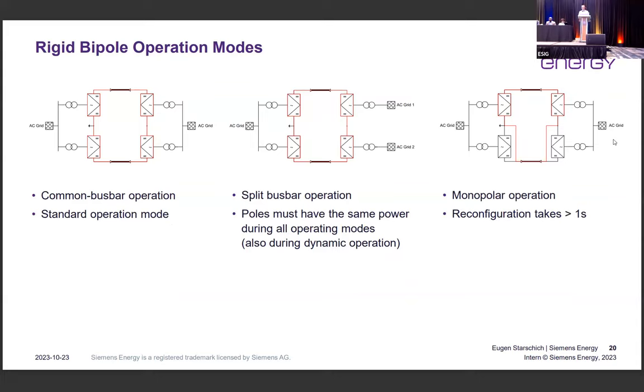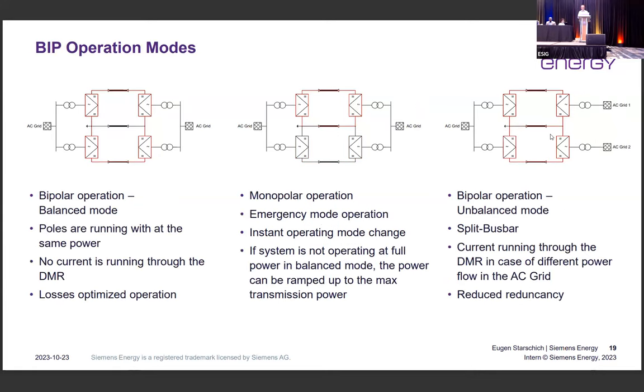In the rigid bipolar operation modes, it's very similar. You can also have a common busbar operation and split operation. One of the other features in the rigid bipolar, and this has been mentioned before, is that in case of a converter fault, you can reconfigure and bypass the faulty converter, as I've shown here, and then you can still transmit at least 50% of the power. So you've got a redundancy in the converter itself, but, as I said, not in the DC line itself. The big difference is that with the bipolar operation mode with dedicated metallic return, the changeover to the monopolar operation happens instantly. There you don't need any reconfiguration, so it happens pretty fast.